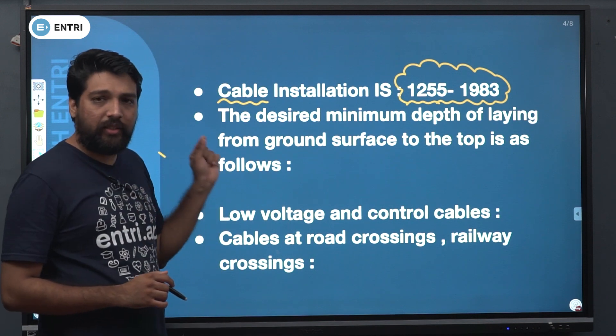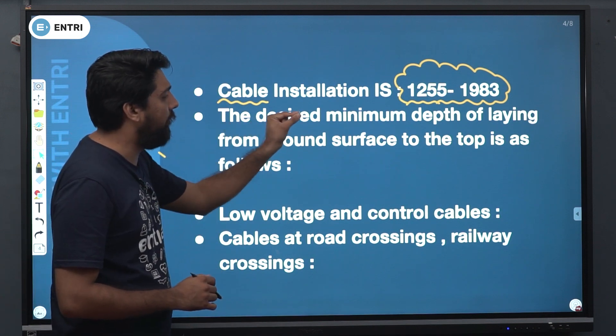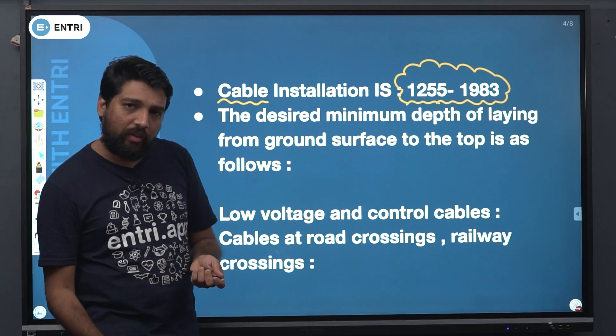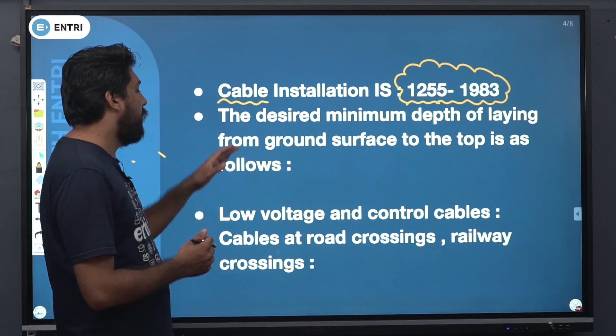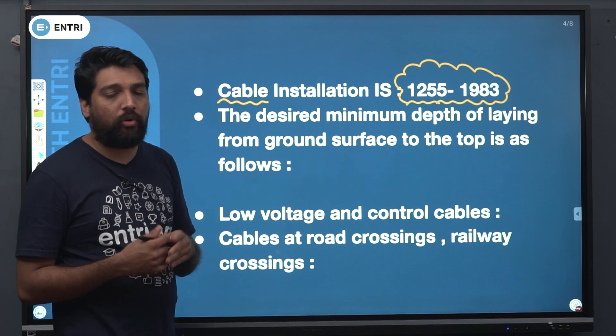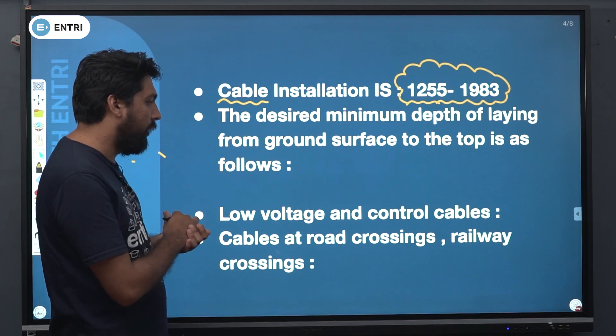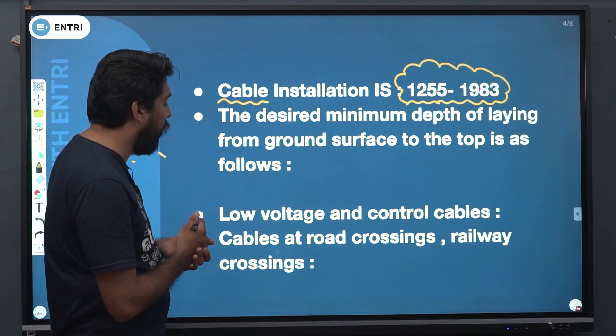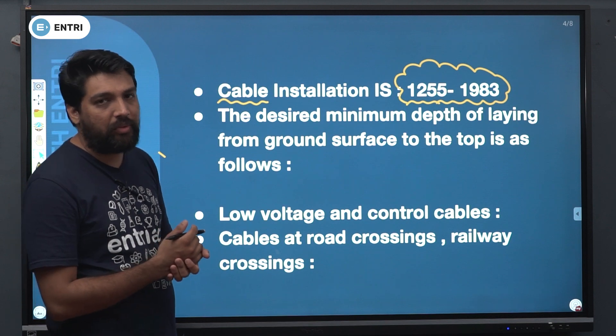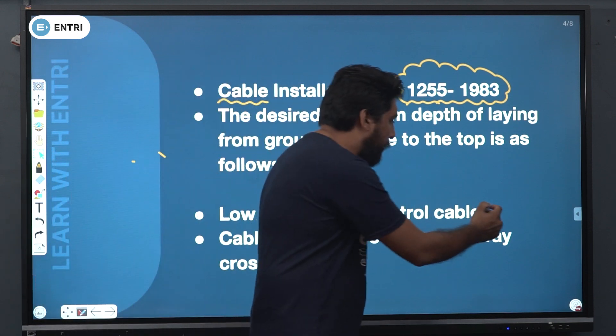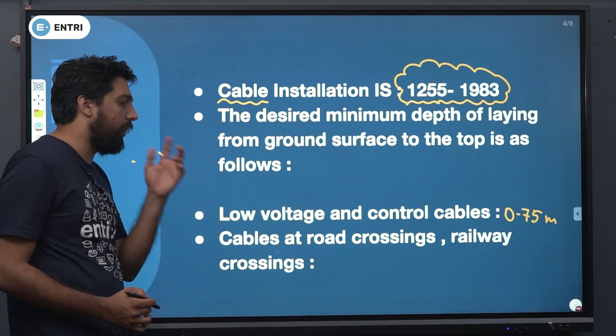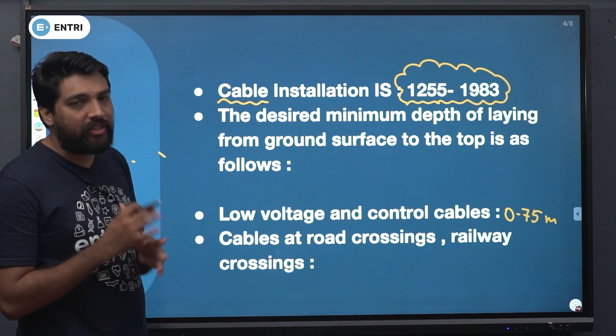Yes, the question is this one. The desired minimum depth of laying from ground surface — you can use the cable to the ground surface. From surface to the top is as follows. If you have a question about low voltage and control cables, the depth should be 0.75 meter. So, low voltage and control cables are 0.75 meter.